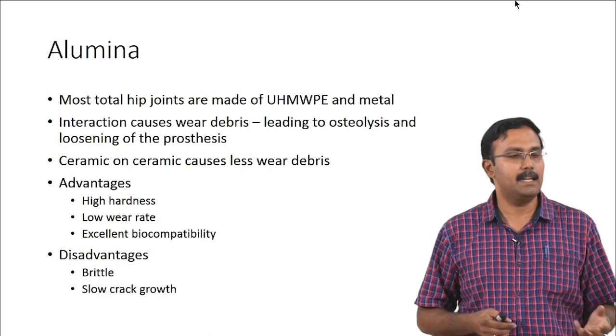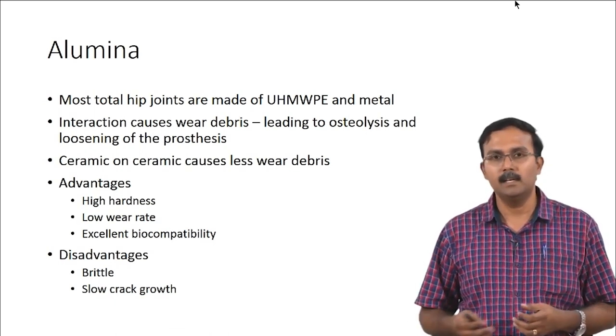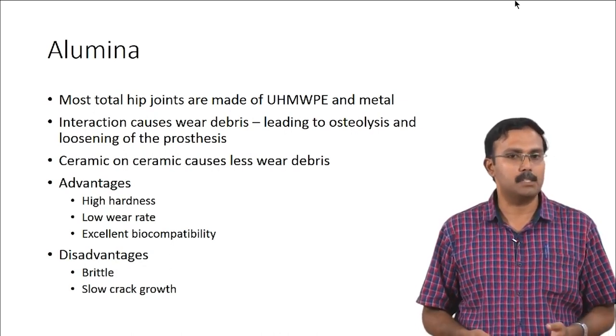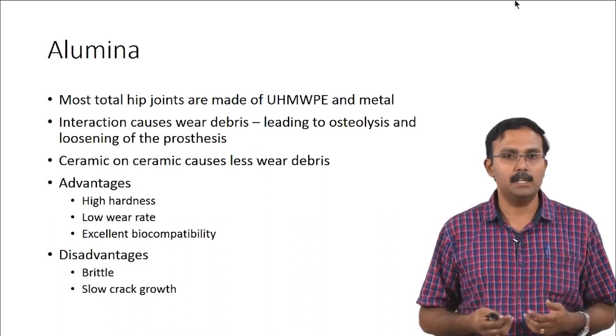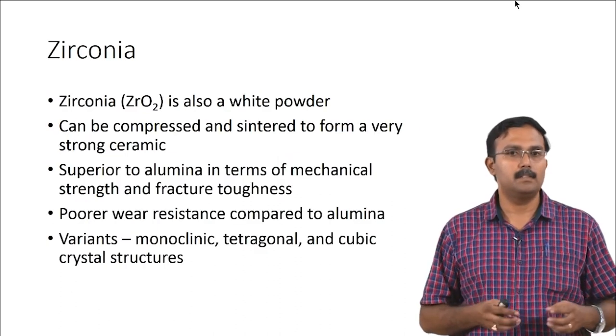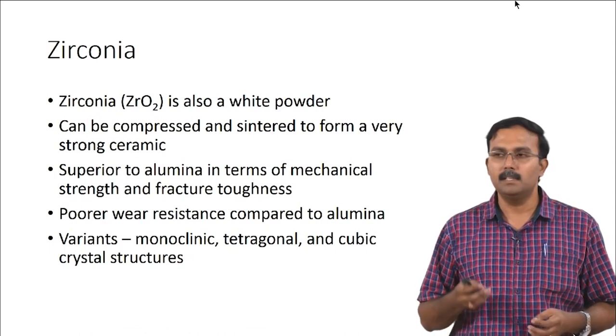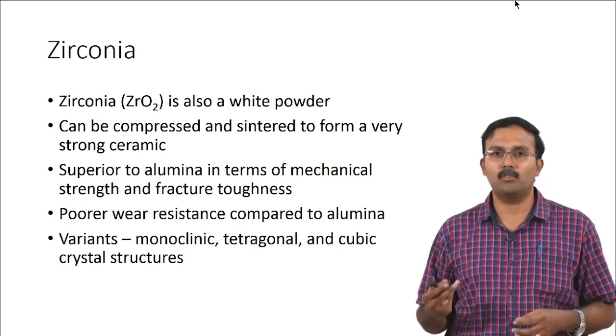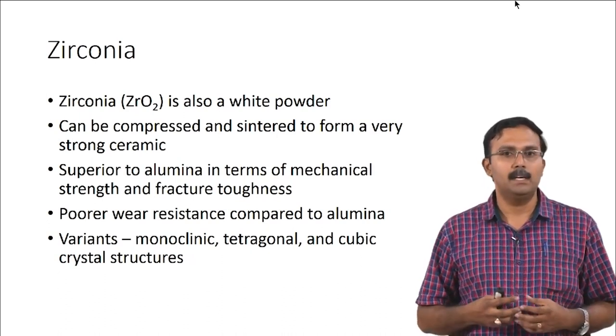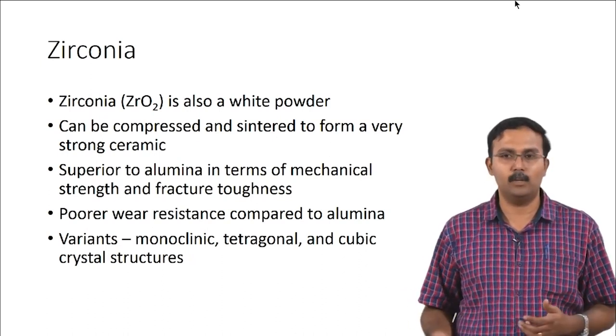The advantage of alumina is its very high hardness and very low wear rate, as well as excellent biocompatibility — it does not cause any inflammatory responses. The disadvantage is it is brittle and can cause cracks. Zirconia is another ceramic which is also a white powder that can be compressed and sintered to form a strong ceramic. Its mechanical strength is better than alumina and its fracture toughness is also better; however, it does not have the same wear resistance as alumina, causing more wear debris under friction.